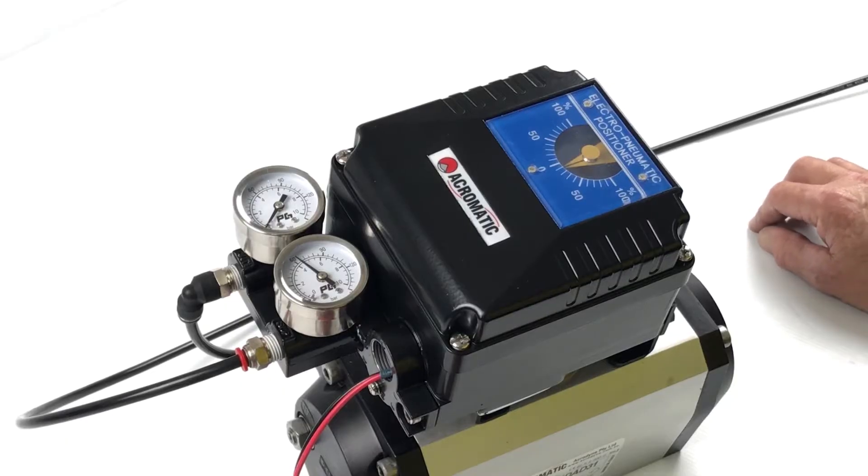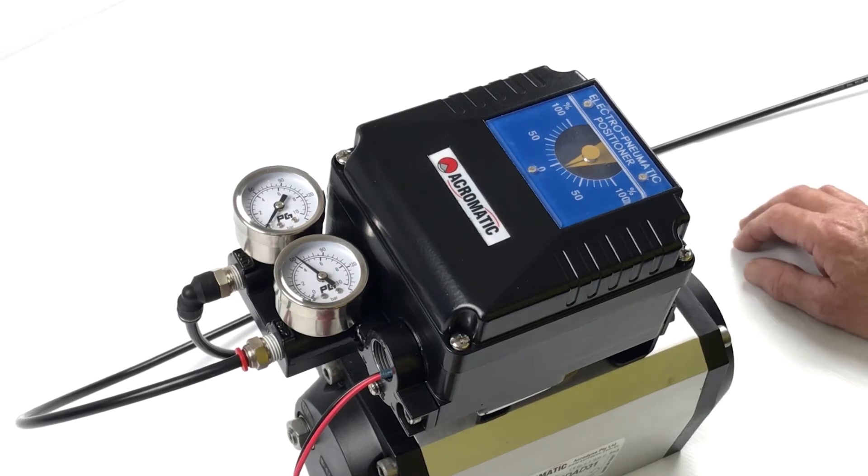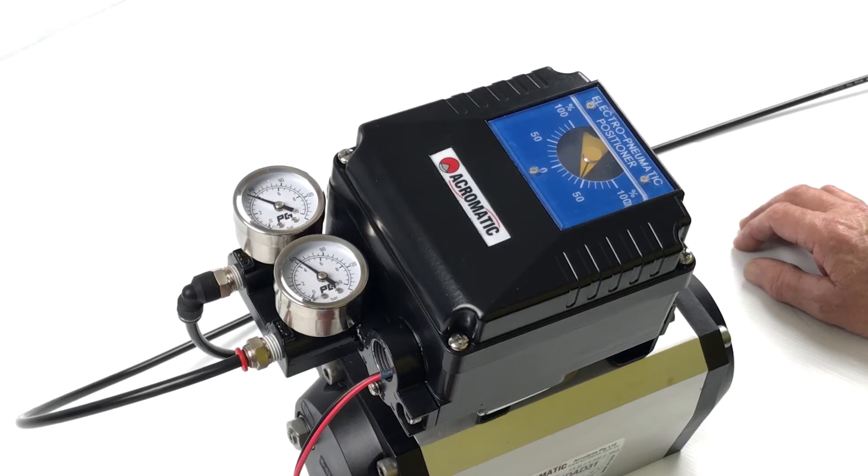This is an Acromatic electro-pneumatic positioner. First we'll check the position of where it is at the moment. We're putting a 4-20mA signal. This one's quite close but not quite accurate.